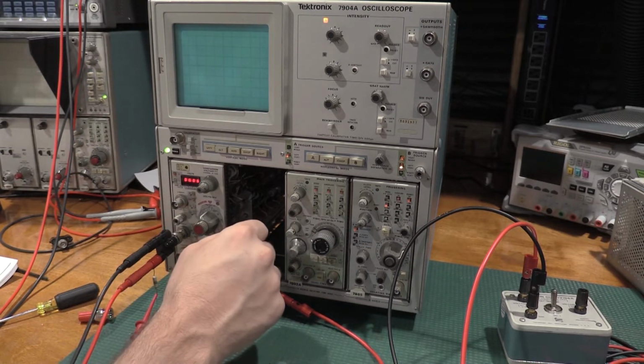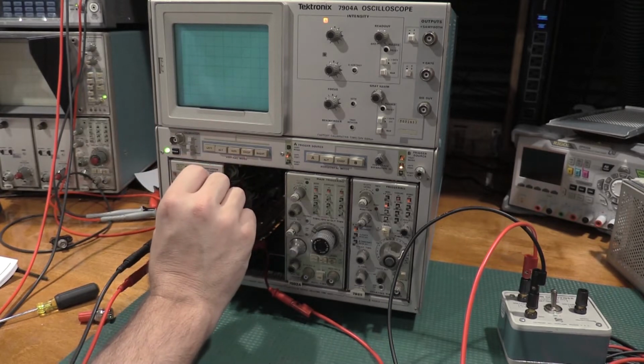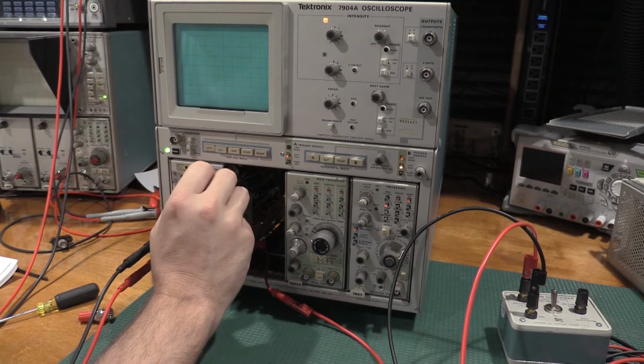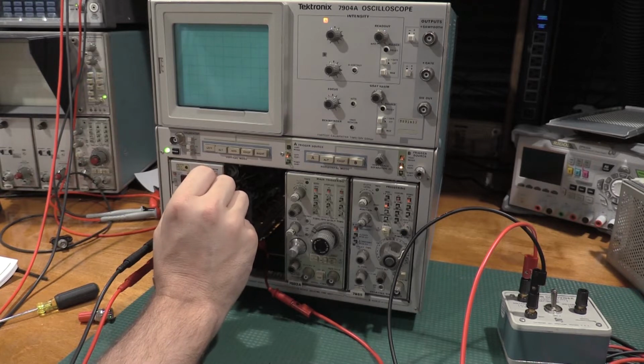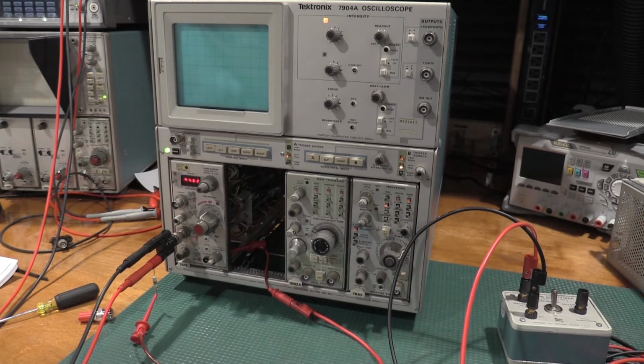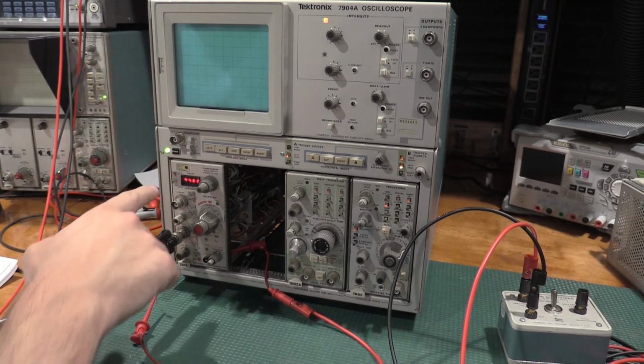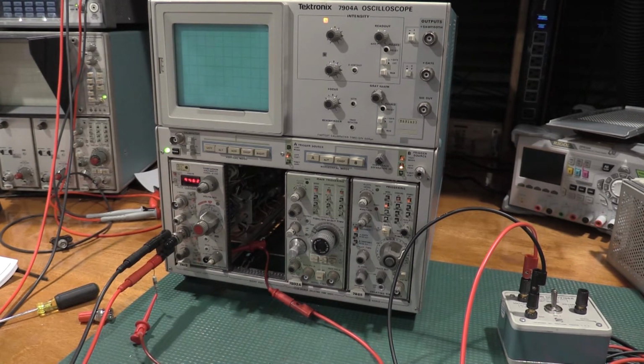Set that DC. This one's a lot more sensitive. Okay, there we go. So this is what my reading is. Not that that matters for this test too much. Yep, we make spec. I went from 4.99 to 4.96, so we're out by about 30 millivolts. So that is good. We do not need to adjust anything there.